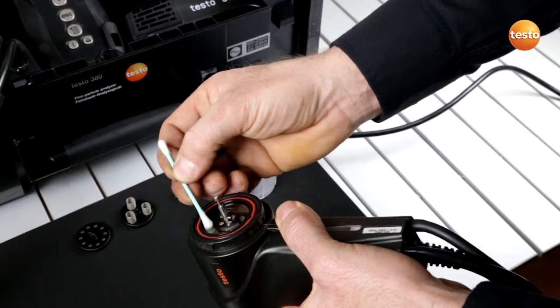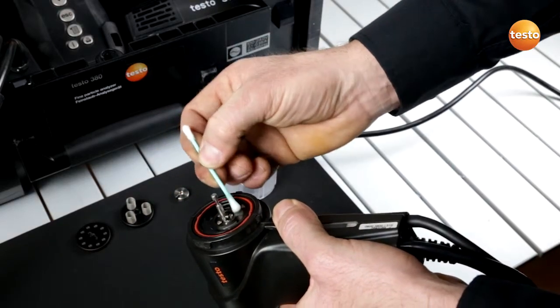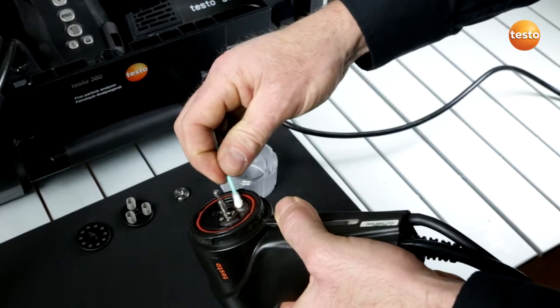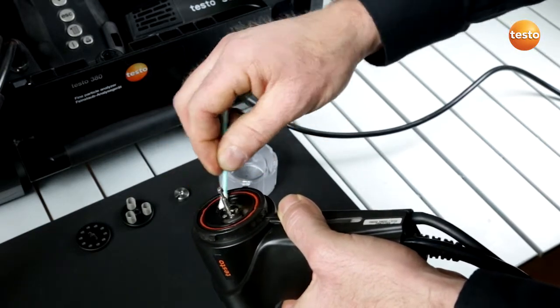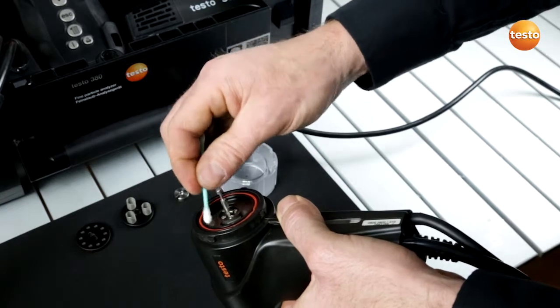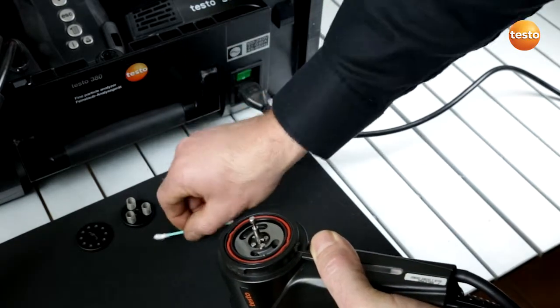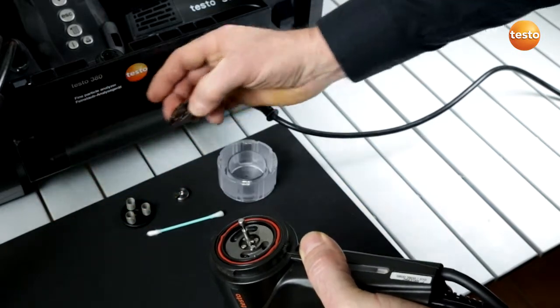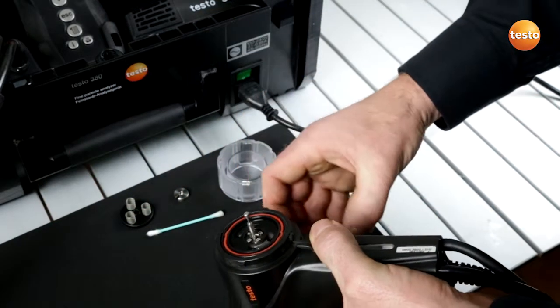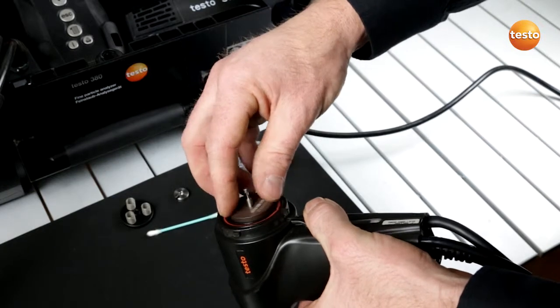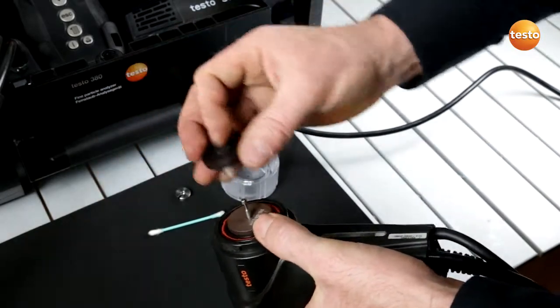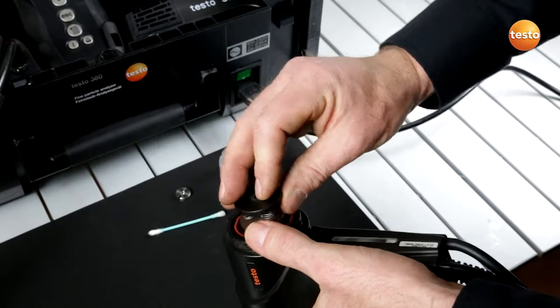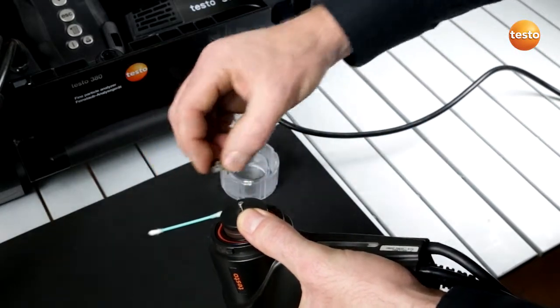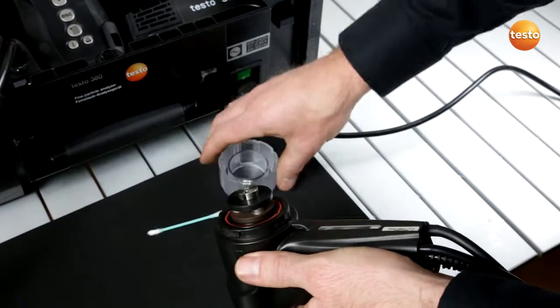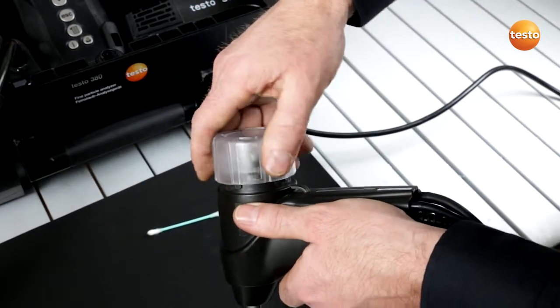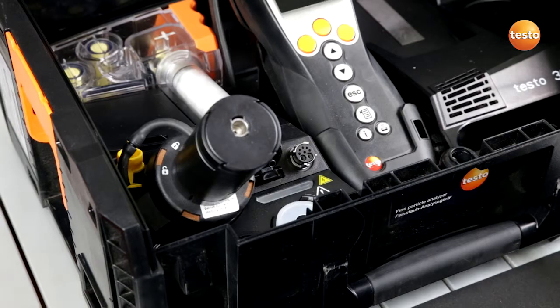The cleaning process is carried out here too, and rub dry again using the dry end. Once a visual check shows that everything is clean, you replace the rotation disc, engage the locking mechanism, and close the cover. Now I'm going to clean the sensor module.